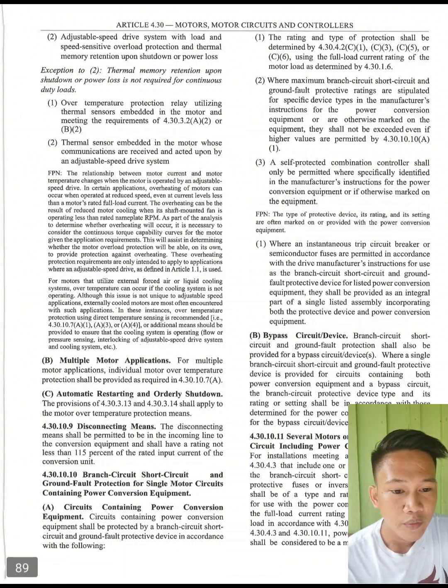So next we have 4.30.10.11, several motors or loads on one branch circuit including power conversion equipment. So, for installation meeting all the requirements of 4.30.4.3 that include one or more power converters, the branch circuit, short circuit, and ground fault protective fuses or inverse time circuit breakers shall be of a type and rating or setting permitted for use with the power conversion equipment using the full load current rating of the connected motor load in accordance with 4.30.4.3 for the purpose of 4.30.4.3 and 4.30.10.11. Power conversion equipment shall be considered to be a motor controller.